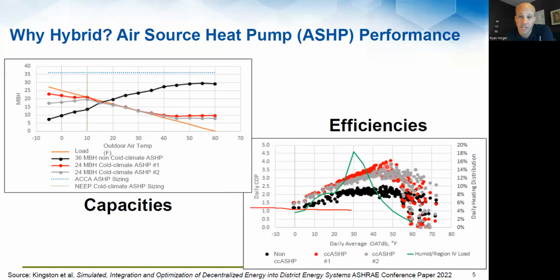Whereas the cold climate ones, which are typically inverter driven and stuff like that, are more efficient all the time, but specifically more efficient when I'm at 25, 30, 35, 40 degrees. They have a pretty good efficiency because they're not being oversped. They're being ramped down because they're inverter driven at that point. And as outside air temperature drops, so does their efficiency. And they end up just a little bit better than these regular traditional ones. Although I can get more BTUs, but not necessarily a ginormous leap in efficiency.